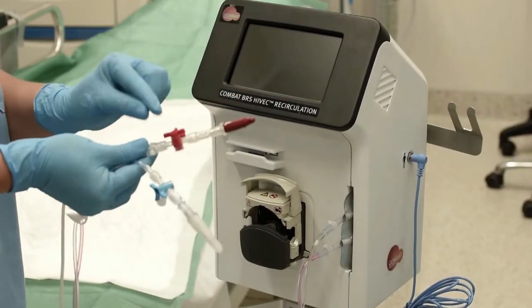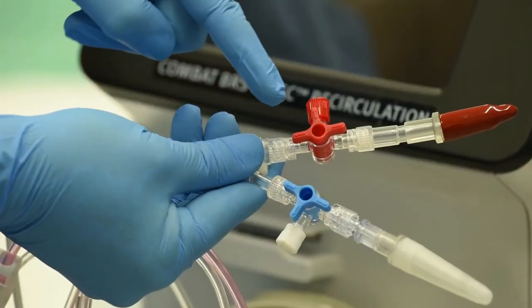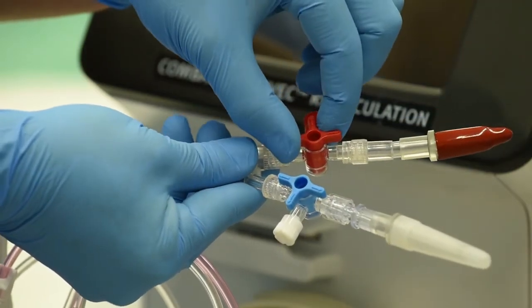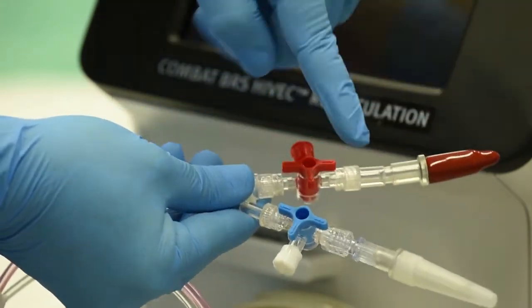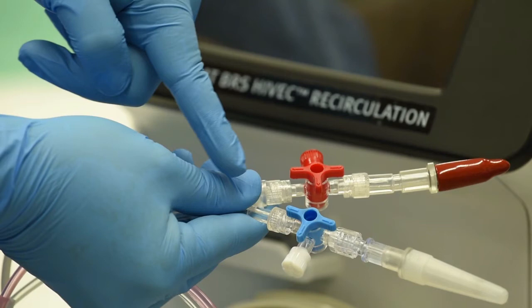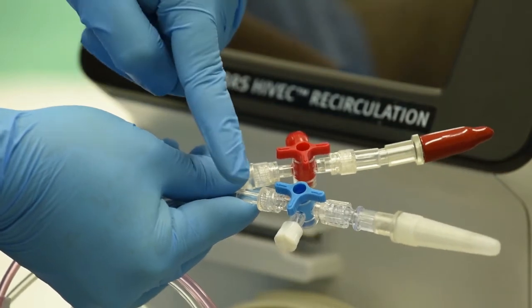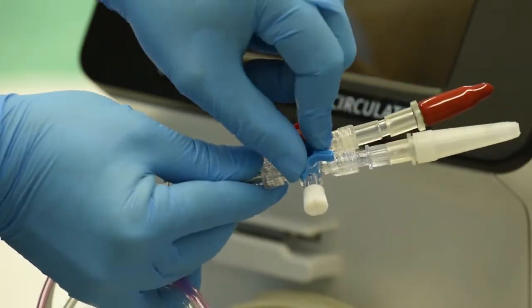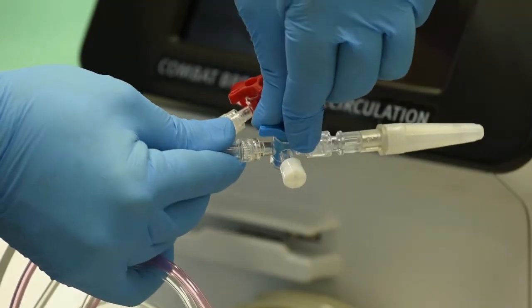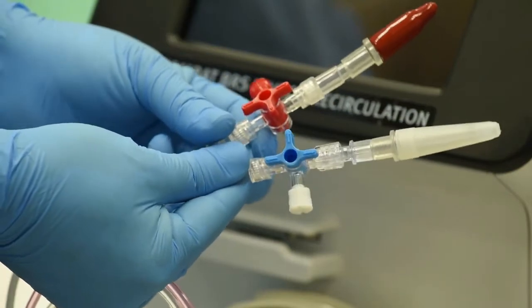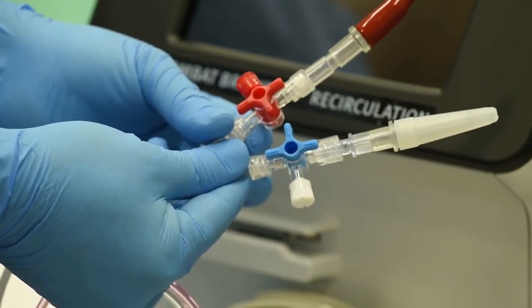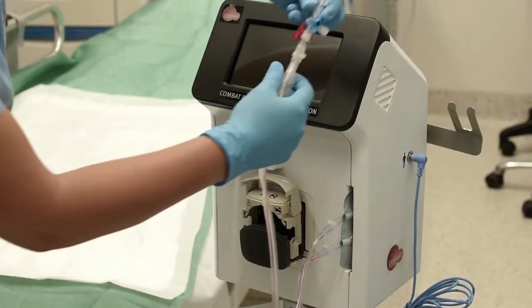Adjust the red drainage port 3-way stopcock from the factory sterilization position to the recirculation position. That is, open to the catheter and open to the system, but closed to the drainage port. Turn the blue instillation port 3-way stopcock so that it is open to the system and catheter but closed to the port. Place the disposable set on the hook support attached to the side of the unit.